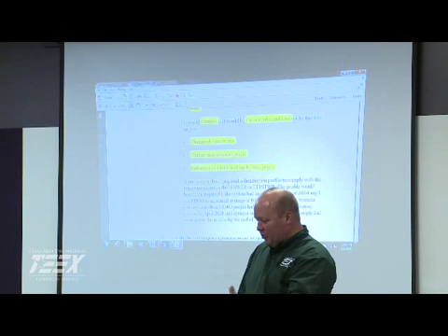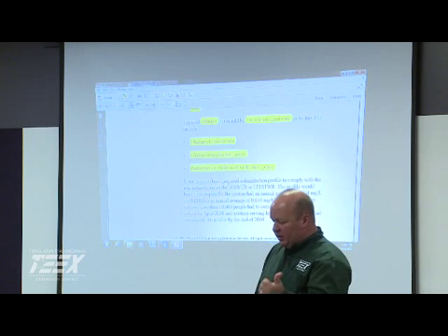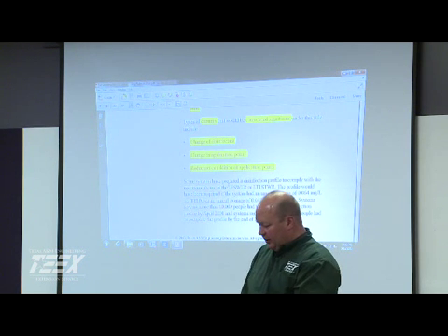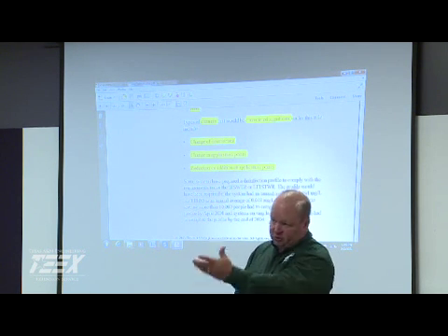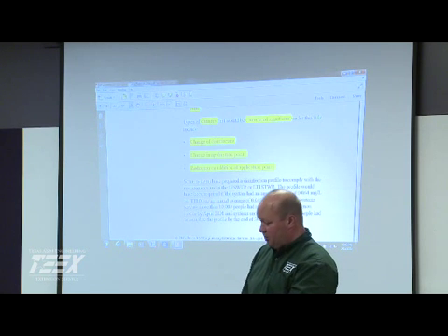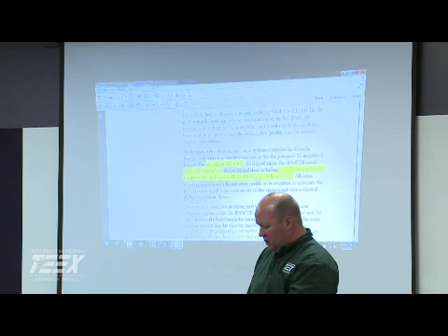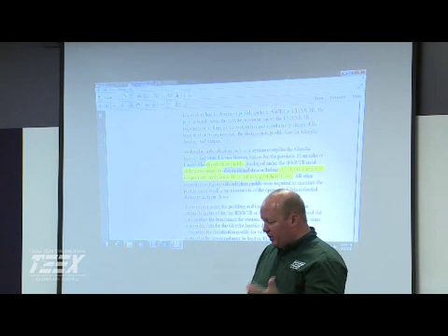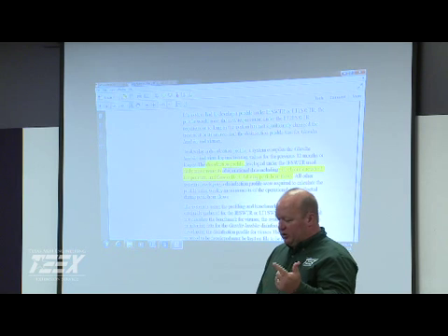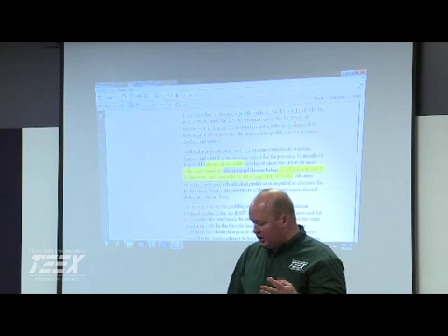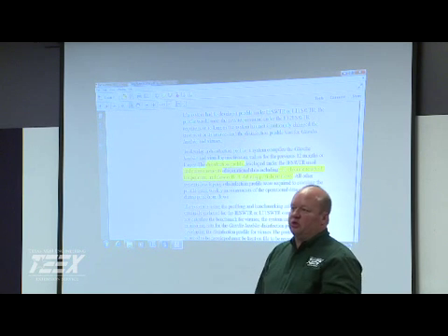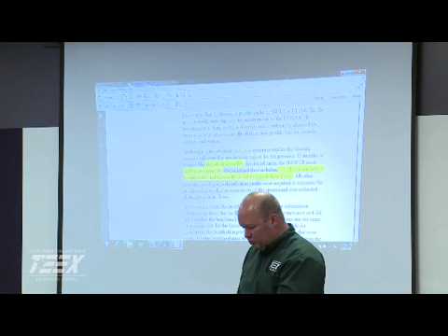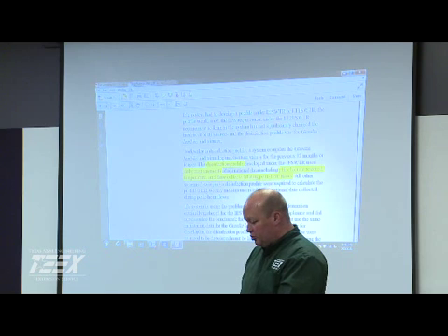Good. So when we look at our types of changes, again, the main thing is the change of the application point, because that's going to affect your CT time overall. That's going to be a big component of it. Then it talks about if you are doing a disinfection profile, you got to do daily measurements, and you look at pH, residual, temperature, and then you need to collect those during your peak flow, because that's going to be your highest demand or the shortest transit time into your facility.